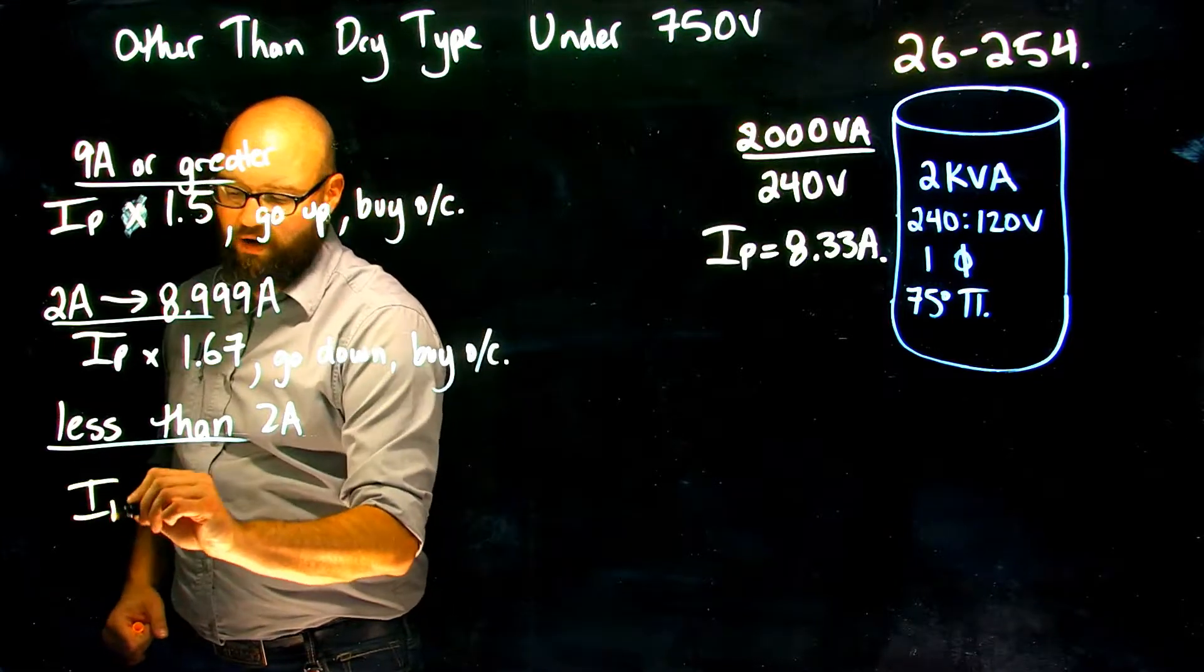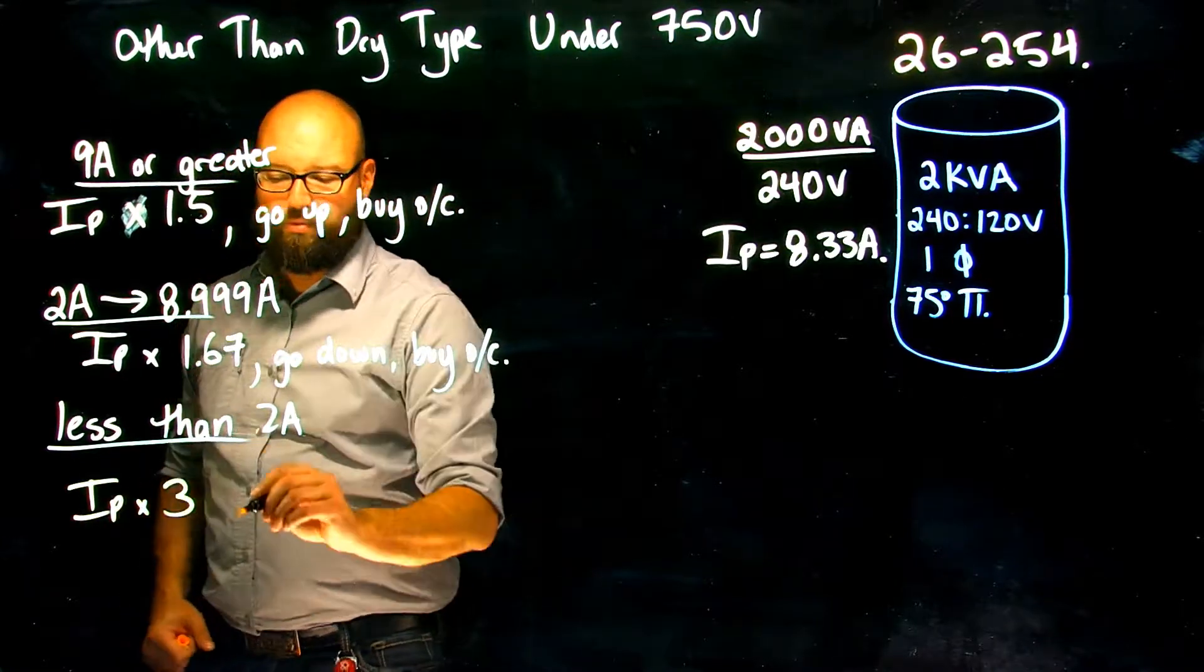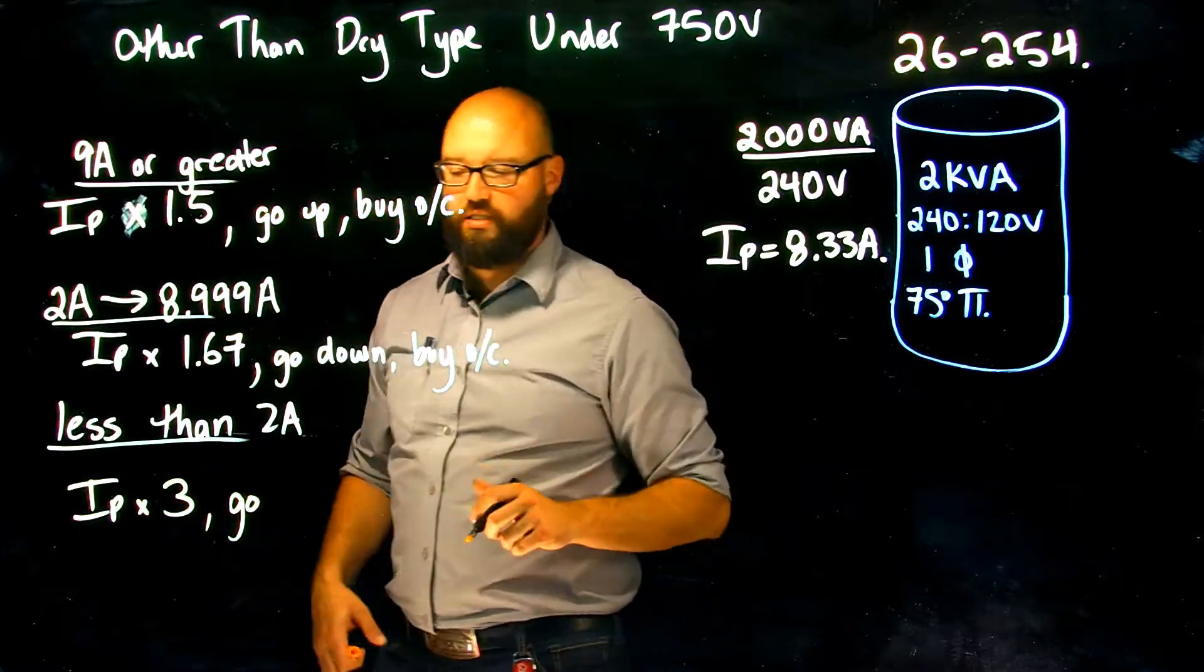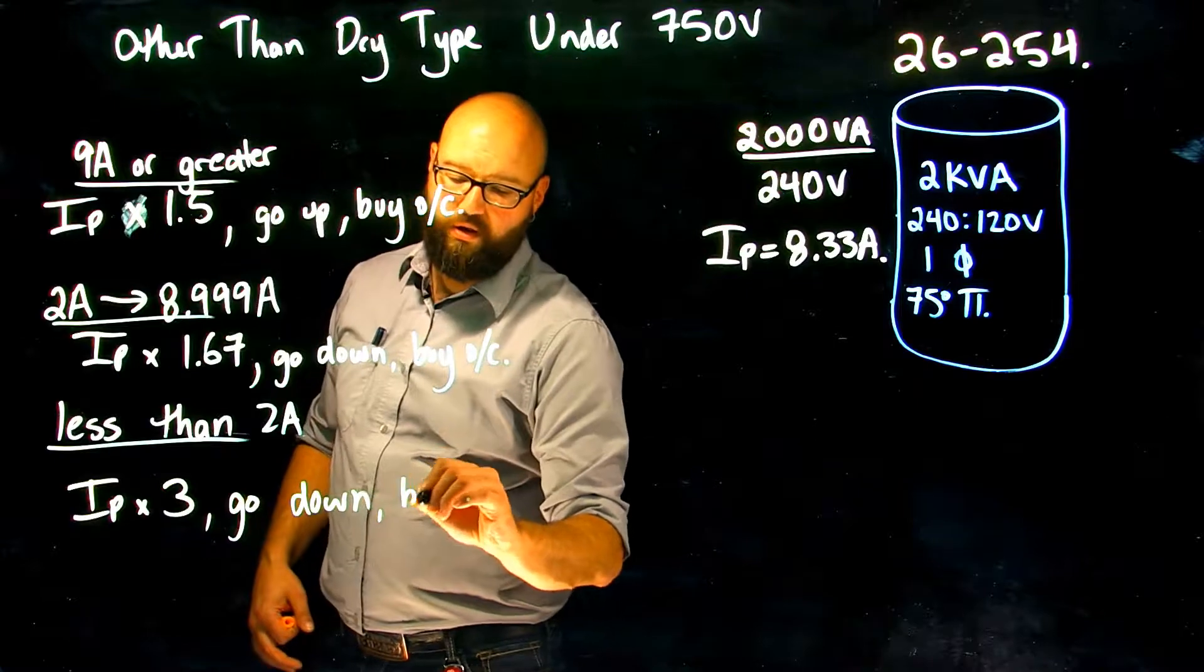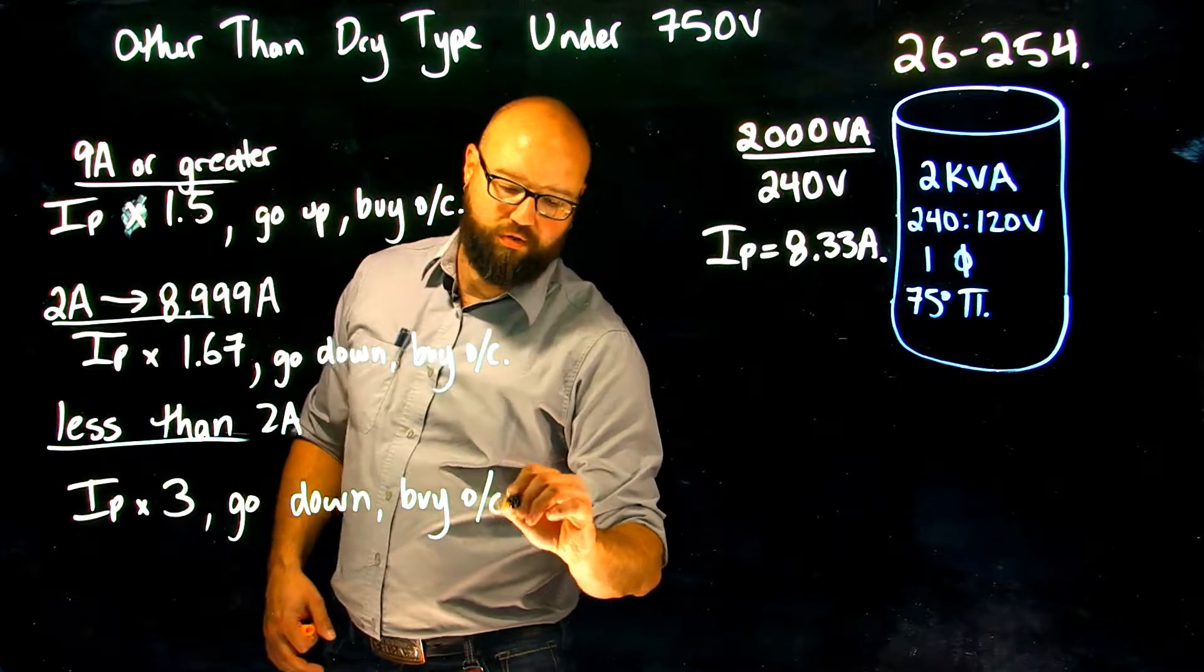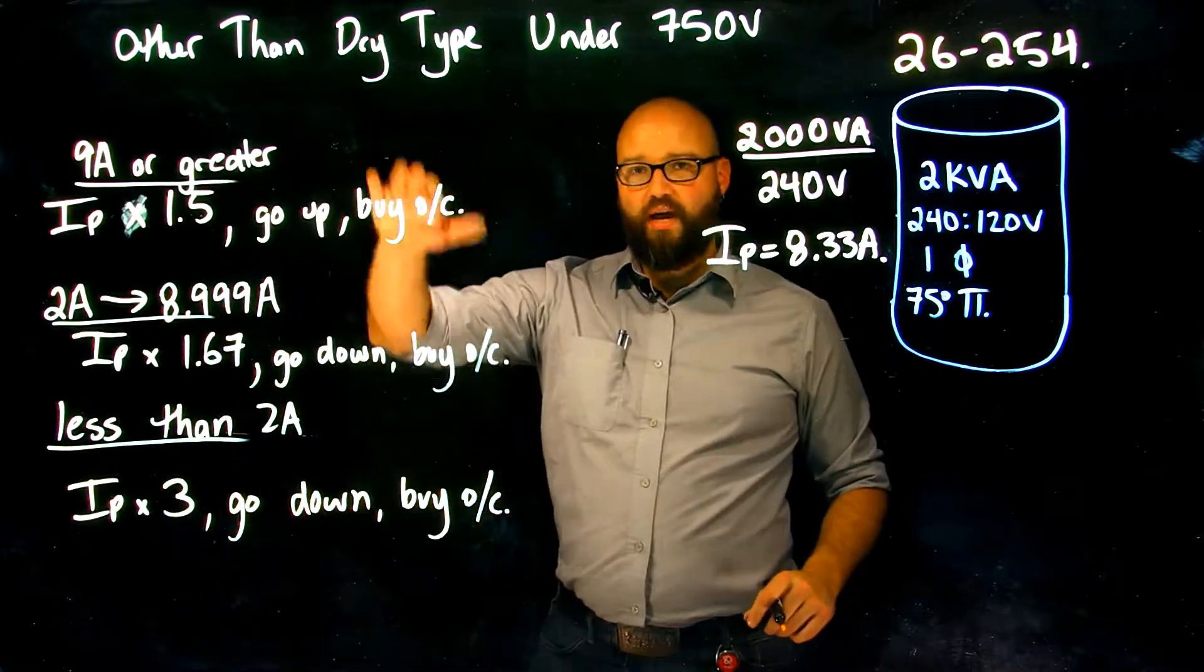So if it's less than 2, I primary times 3 or 300 percent, and again no exceptions to this. It tells me I cannot exceed, go down, buy overcurrent.